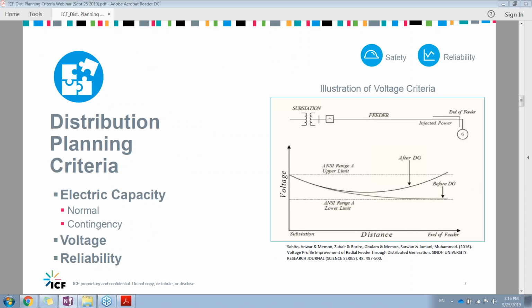The first, electric capacity, has long been the focus of planning processes. The goal is to serve the peak load customers may demand at any time during the year, in both a normal configuration—a sunny day with the system completely intact as designed—and contingency, or backup, configurations that might result from equipment failures or the need to perform maintenance on a specific part of the system.